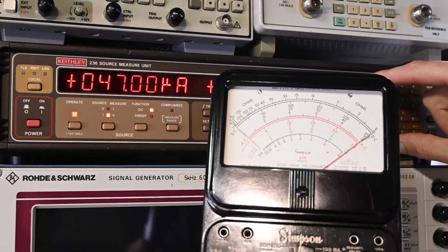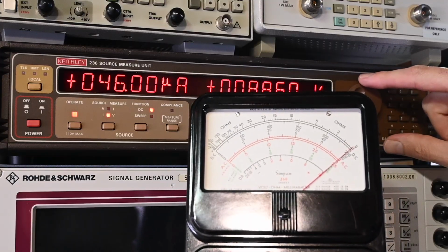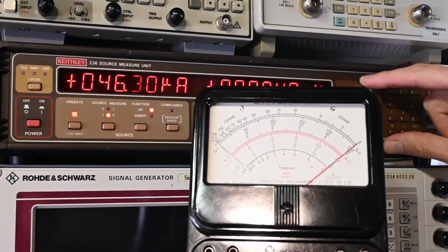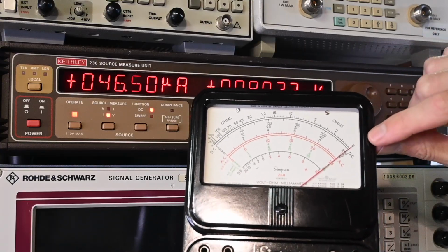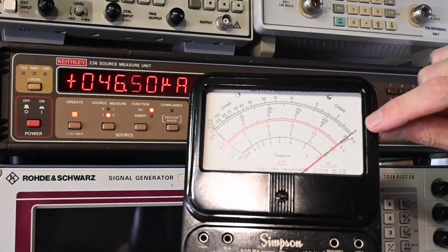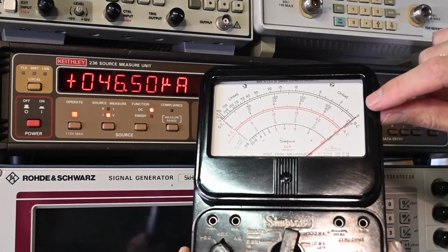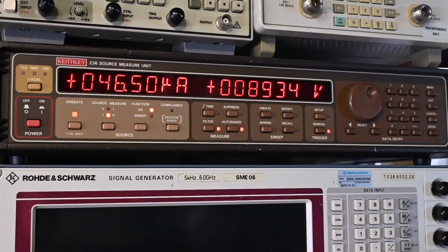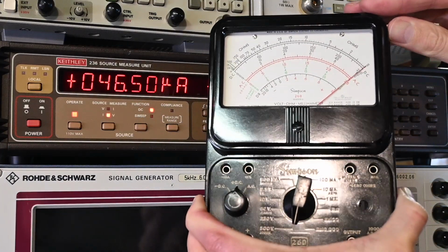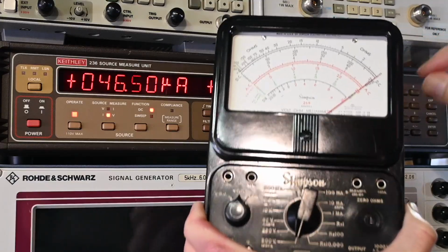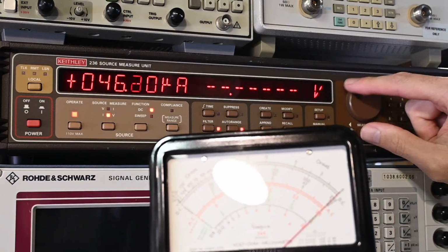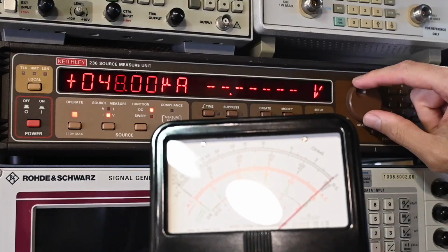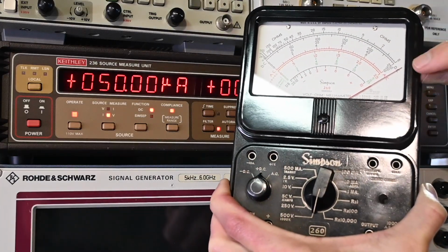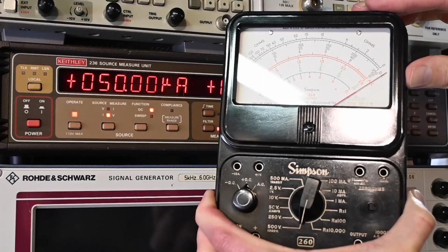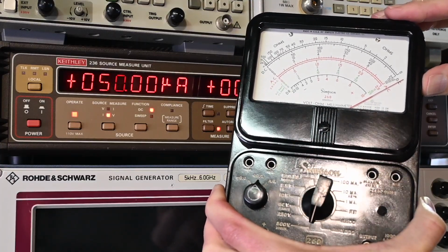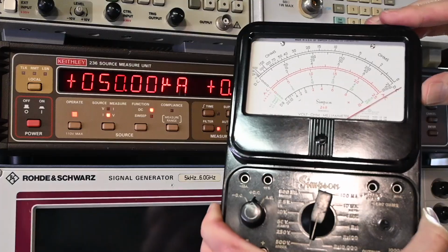Right there, go down, and let's move this over to a little bit finer resolution. To my eye, it looks like that's right on the last tick mark on the dial. Okay, so it looks like 46.5 microamps. That makes sense. That's just a little bit less than the 50 microamps full scale deflection. If I go all the way over, just turn this down, 46, 47, 48, 49, and 50. You can see what happens at 50 microamps, it does in fact go off the end of the scale. So perfect, the meter is working the way that it's supposed to at this point. That's very good to see.